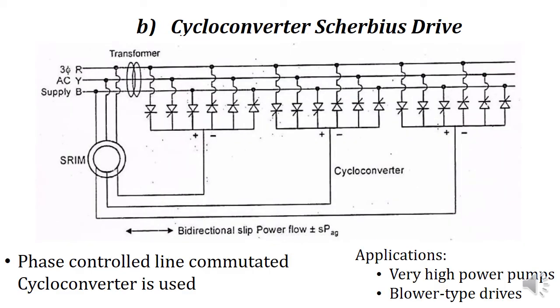Next we will discuss the cycloconverter Scherbius drive. The basic circuit consists of a slip ring induction motor, a phase-controlled line-commutated cycloconverter, and a transformer. This transformer is necessary in order to minimize the rating of the thyristor switches; otherwise we would need thyristor switches of very high rating to connect to the supply mains. These drives are used only for very high power pump and blower type applications.